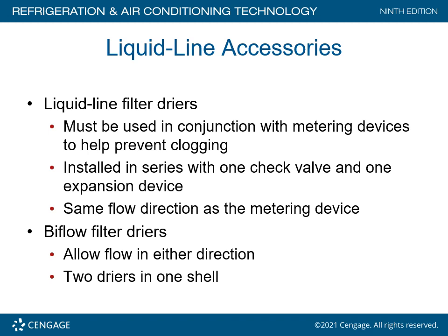This is installed in series with a check valve and one expansion valve, in the same flow direction as the metering device. The bi-flow filter dryers allow the flow in either direction. It's basically two dryers within one shell. So when you work on heat pumps, when you're doing service work, compressor replacement, or valve replacement, you must have a bi-flow dryer. Please don't forget that.